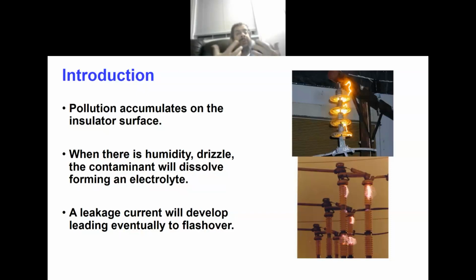The power system is protected. There is a protection system that will disconnect the line when these things happen, to prevent fires. However, disconnecting the line is an interruption to the power system, and we lose power. This is one of the major reasons why we might lose power in overhead lines. 60 to 70% of overhead line failures are because of insulator flashover. Now the question is how we can control this, since we don't want this current to develop on the surface.